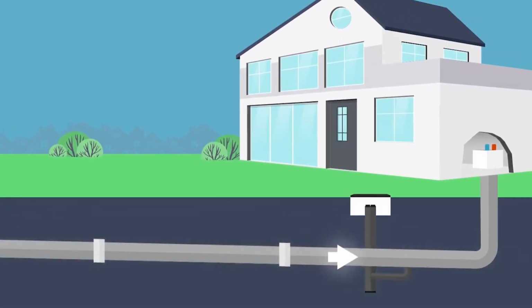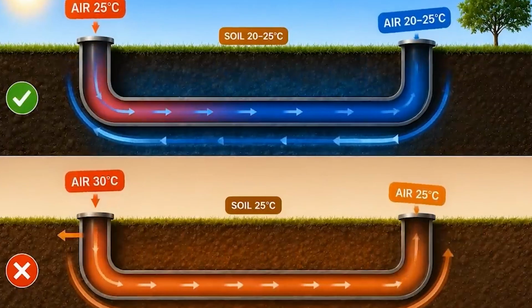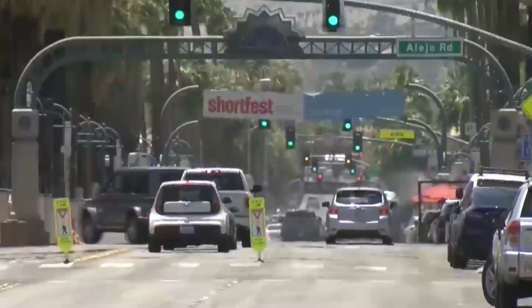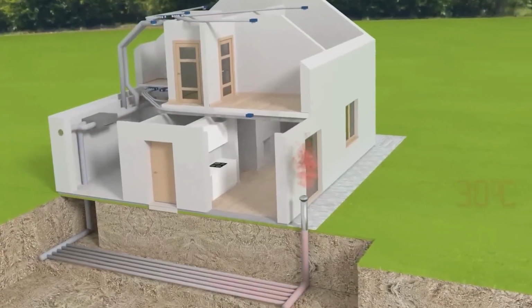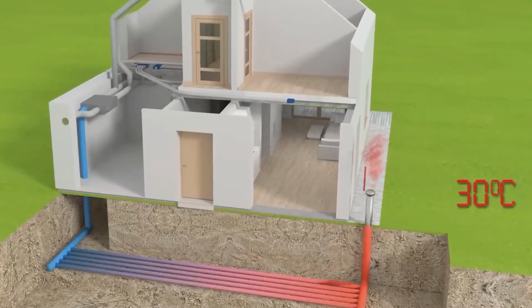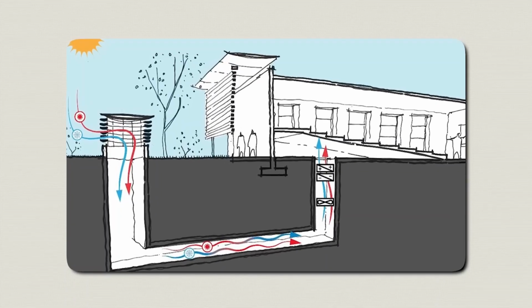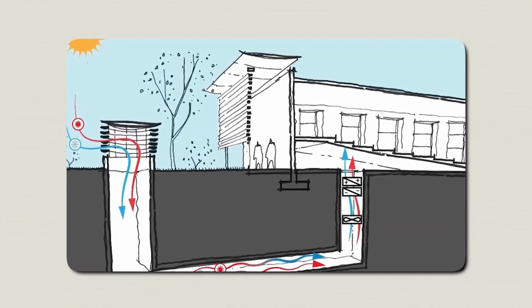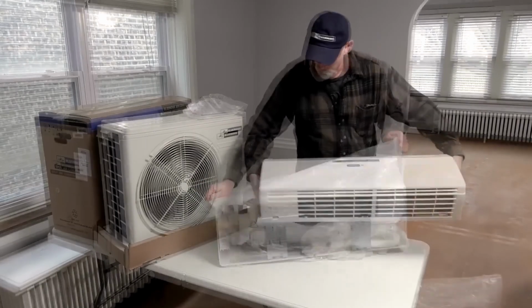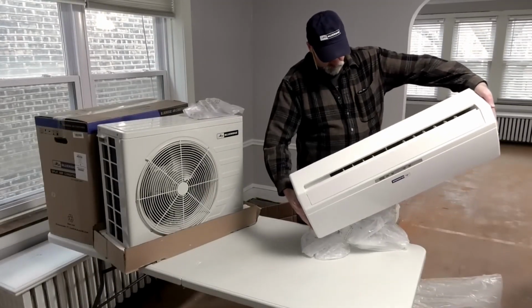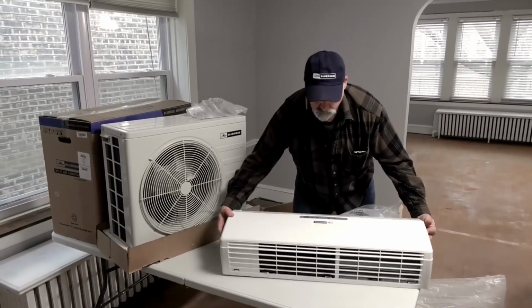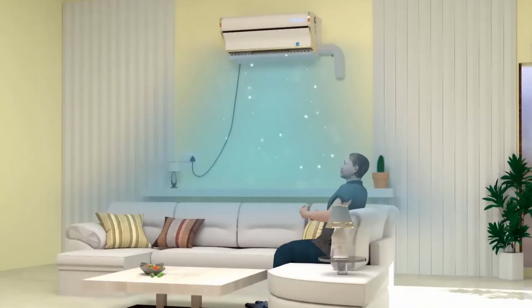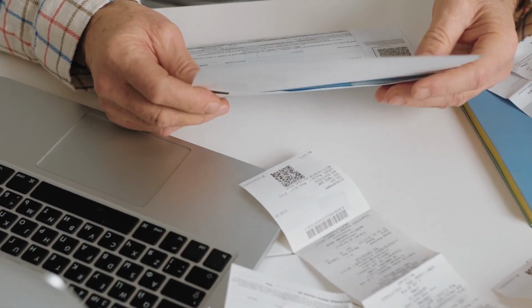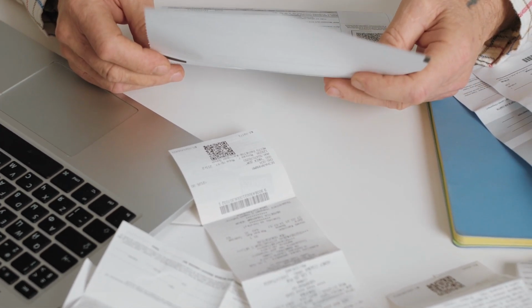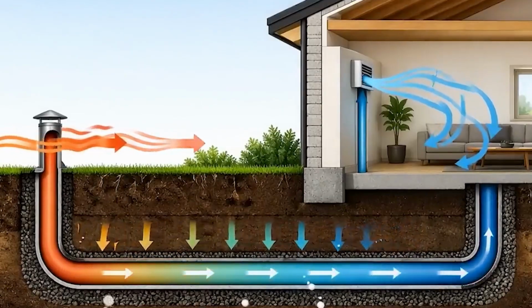Their conclusion? The system's performance scales directly with pipe length and burial depth, and on peak summer days, the temperature differential between incoming air and the surrounding soil drives the system at its hardest exactly when you need it most. And crucially, that self-reinforcing behavior is what separates it from mechanical cooling. On the days your air conditioner is running at maximum load and driving your electricity bill to its monthly peak, an earth tube is at its most effective.